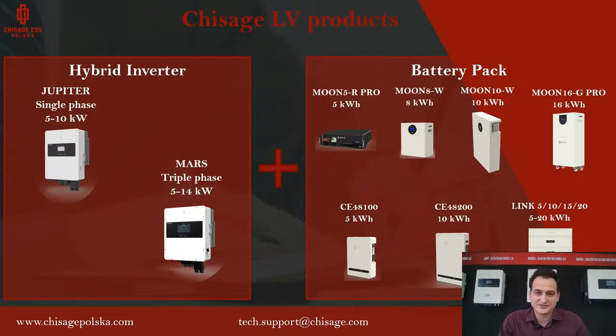We have the CE48 series, 100 and 200, 5 and 10 kilowatt hour batteries. These batteries are IP65, so we can basically mount them in any wet room and wet conditions, and can mount outside. Of course, we have to take care about temperature because batteries cannot fully work below 0 degrees. And we have Link 5, 10, 15, or 20. Link is a battery where we put a footer, then we put up to 4 battery packs and the connection box at the top. So we can do from 5 to 20 Link like this. And any of these batteries, we can connect up to 15 in parallel. So for example, Moon 16, we can connect 15 Moon 16s in parallel to one inverter.